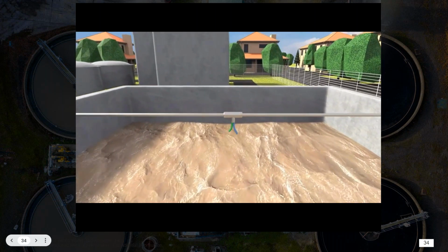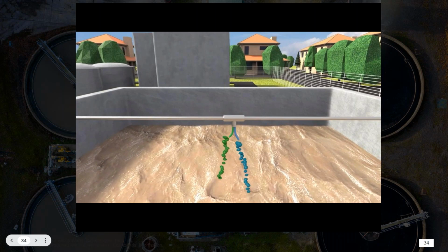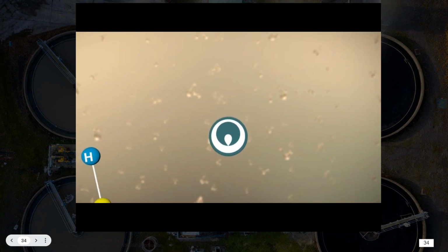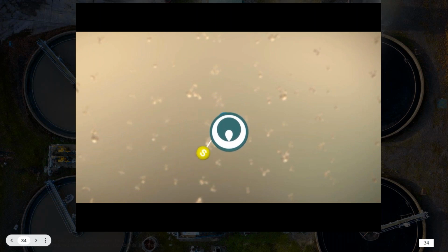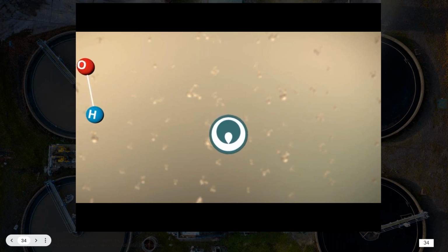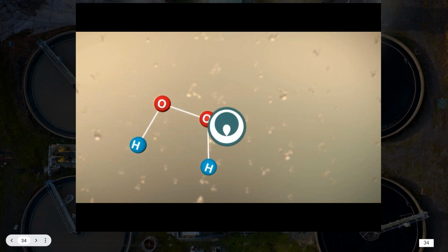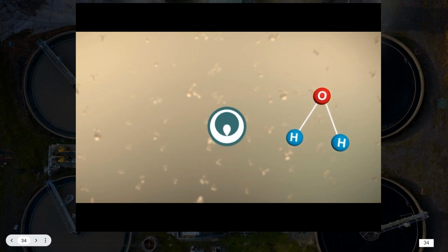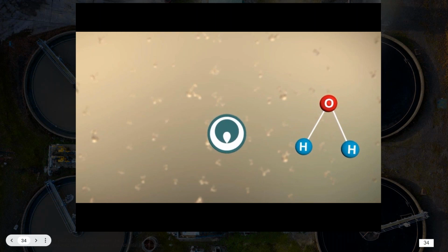The 2 products are introduced into the wastewater pipe or a vessel or a reaction tank in an area of good mixing. The first step will be the reaction of Hydrex with the sulfide, converting the dissolved sulfide into elemental sulfur. The next step is the regeneration of the Hydrex reactant by either peroxide or oxygen. And when peroxide is used, the only byproduct is water. This regenerated Hydrex reactant then goes back into the redox process again and again and again.